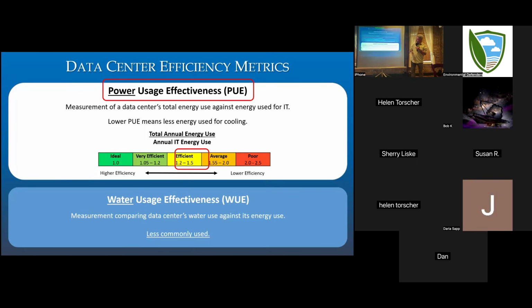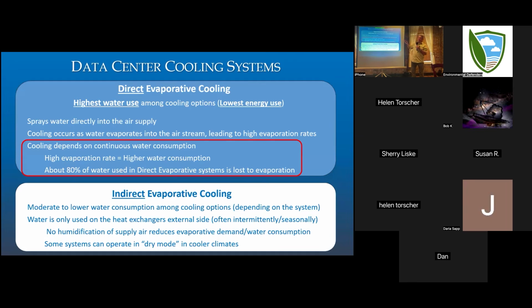So when we talk about different types of cooling systems, direct evaporative cooling would often be referred to as swamp coolers, and they use a ton of water. These things have to constantly provide water for cooling; they're basically spraying water, and it's the evaporation of that water that provides the cooling. As that water evaporates, that increases the consumptive use of water. There is also indirect evaporative cooling, which could be much more efficient, but that is going to increase energy usage.